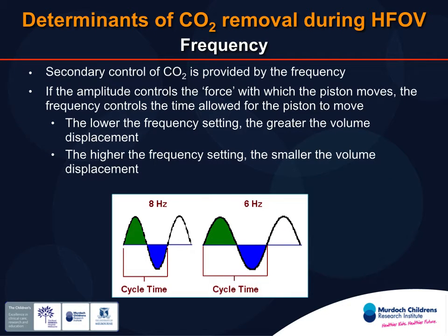So the next thing is the frequency. The frequency is our other control of CO2. If the amplitude controls the force with which the piston moves, the frequency controls the time that the ventilator is allowing the piston to move. So a lower frequency will give you greater volume displacement because of the area under the curve concept, and a higher frequency will give you less volume displacement, but you'll get more cycles in per minute.